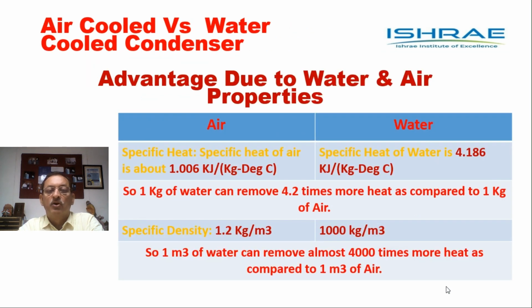Let's now talk about the advantages of these two kinds of condensers because of the properties of water and air. I've listed the properties of air and water in two different columns. The first property that is interesting for us is the specific heat of air. The specific heat of air is 1.006 kilojoule per kg per degree centigrade, whereas the specific heat of water is 4.186 kilojoule per kg per degree centigrade. So we can see that water is almost about 4.2 times higher in specific heat as compared to air. And that means that 1 kg of water can remove 4.2 times more heat as compared to 1 kg of air.